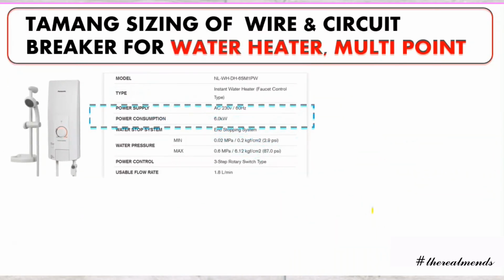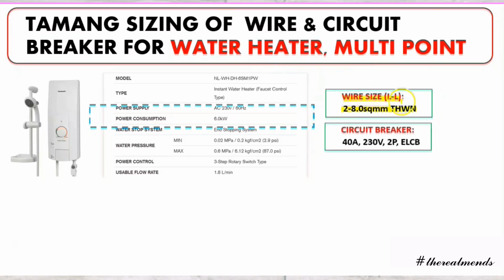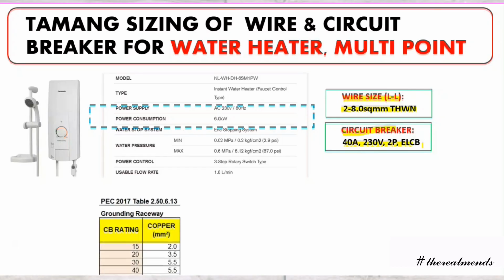Therefore, our wire is two 8.0 square mm THWN. To sum up our computation, again, the wire size is two 8.0 square mm, and our circuit breaker is 40 amperes, 230 volts, 2 pole earth leakage circuit breaker. And if you ask me what the grounding will be, look at table 2.50.6.13 for grounding. If you have a 40 amperes circuit breaker rating and copper wire, our grounding wire is 5.5 square mm.